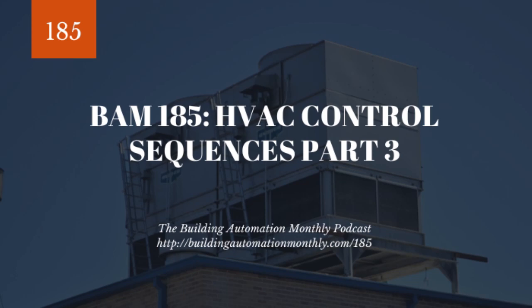So far on our podcast journey here, we talked about space control and we talked about the different variables we control within the space. Then from there, we moved into fan coil units and rooftop units, which are more unitary systems, meaning they typically will be self-enclosed, essentially, controlling their own cooling, their own heating, and typically controlling to a single space. From here, we're now moving into air handling systems. Now, these systems tend to serve multiple zones, and how they do that is either by providing constant volume to these zones or spaces, and then varying the discharge air temperature, or by providing a constant discharge air temperature and then varying the airflow, as we saw in the first episode of this series on VAV boxes.